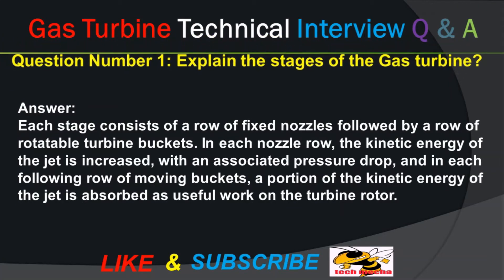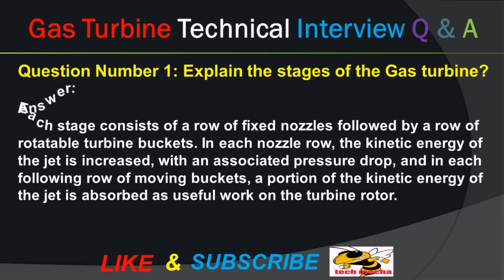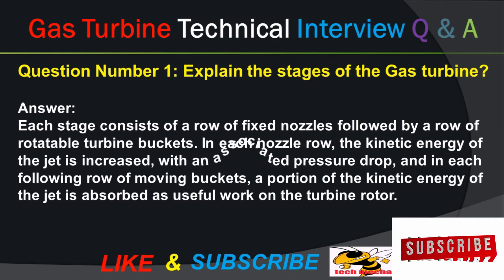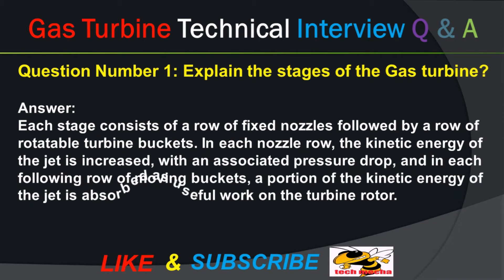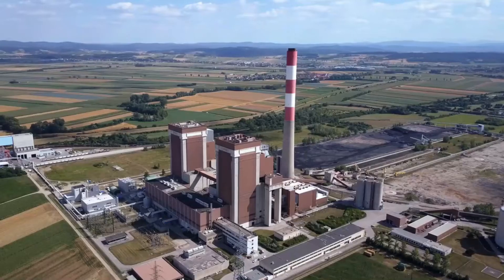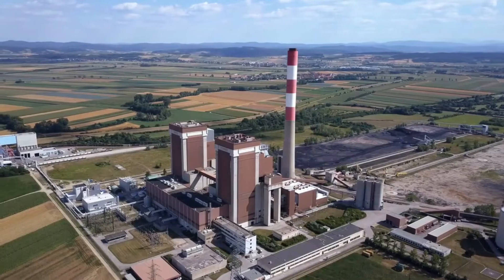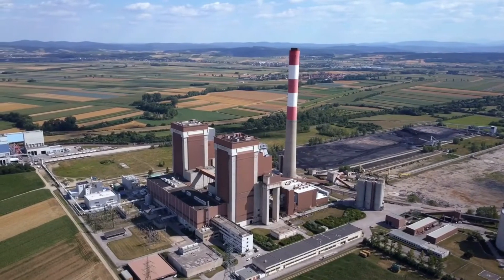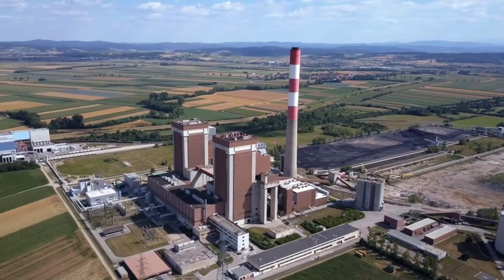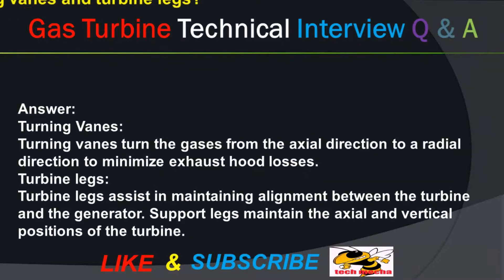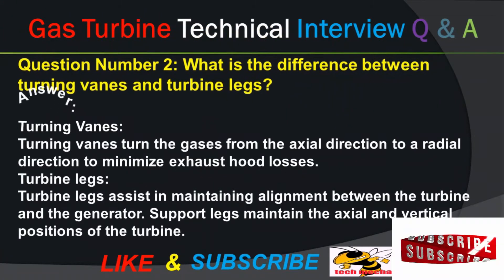Question number one: explain the stages of the gas turbine. Answer: each stage consists of a row of fixed nozzles followed by a row of rotatable turbine buckets. In each nozzle row, the kinetic energy of the jet is increased with an associated pressure drop, and in each following row of moving buckets, a portion of the kinetic energy of the jet is absorbed as useful work on the turbine rotor.